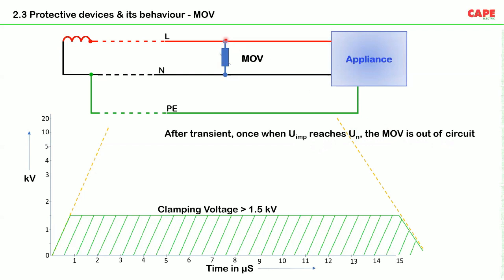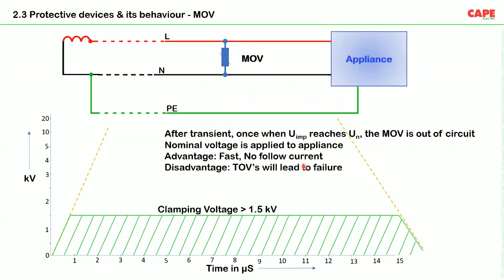That means when there is a high voltage, this device is limiting the voltage to 1.5 kV. Once the transient over voltage is less than 1.5 kV and reaches 230 volt, this device is automatically out of the circuit. Nominal voltage is applied to the appliance, so 230 volt goes directly to this particular equipment. The advantage of this device is that it is fast and there is no follow current. We will see the follow current later on. With this device, temporary over voltages will lead to failure.